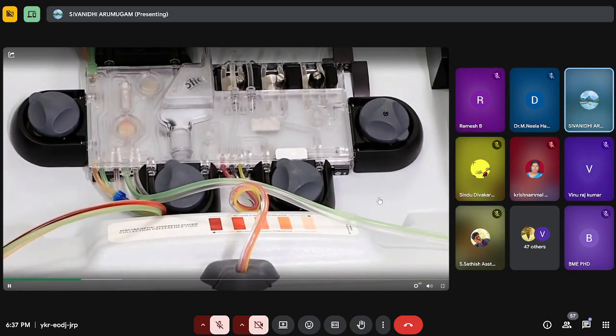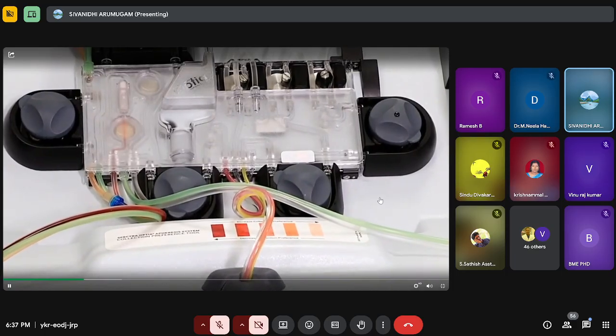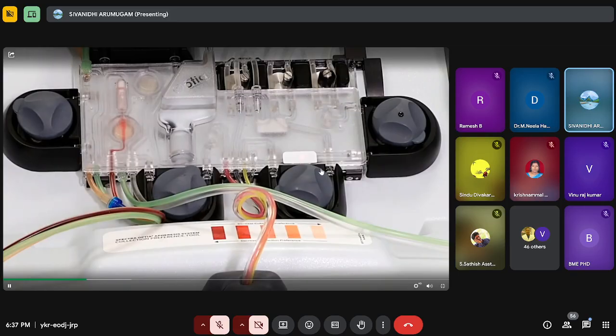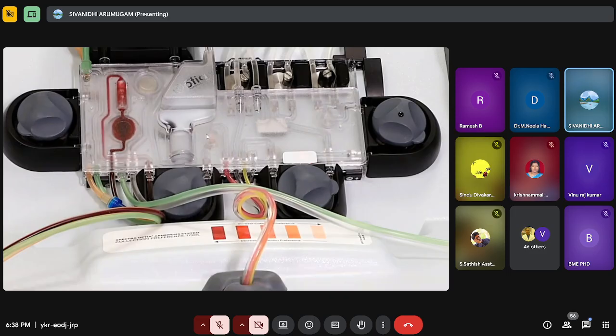When the chamber is full, the system triggers a collection phase. Here you can see this pump is rotating, right? Accumulation cells. You can see this is rotating and this is rotating. It means it is collecting blood and adding AC to it. So the blood with AC is now coming into this cassette, and from the cassette it is going to the centrifuge, and then into the collection bag. The number of times the chamber is filled throughout the run depends on the patient. Now you've seen this flow, no?